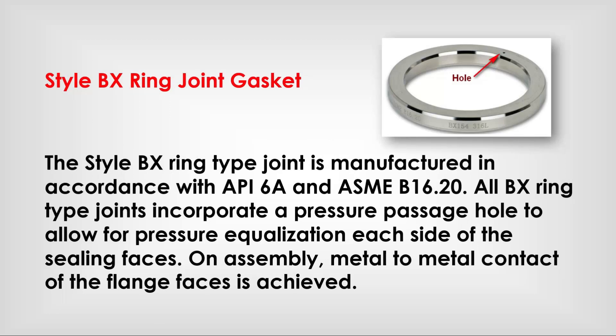Style BX ring joint gaskets: the style BX ring-type joint is manufactured in accordance with API 6A and ASME B16.20. All BX ring-type joints incorporate a pressure passage hole to allow for pressure equalization on each side of the sealing faces. On assembly, metal-to-metal contact of the flange faces is achieved.